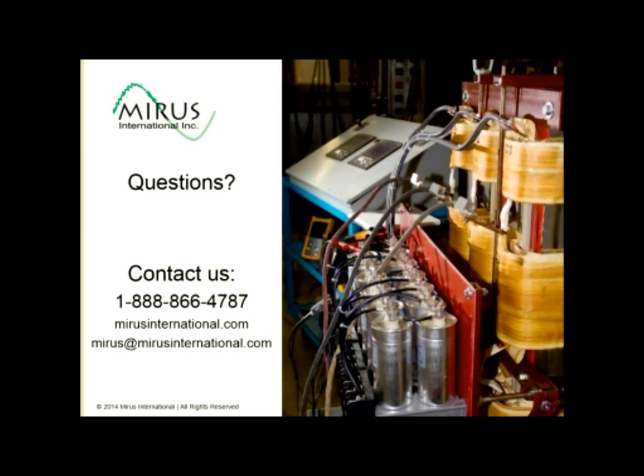There's a question: in a rural area where there are several installations of VFDs with filters and all the VFDs are off, would the capacitive reactance become an issue for the supply network? It's a good question. It really depends how many filters there are on the system, but typically the power system can handle some leading power factor, and if the power system is a quite stiff system, a fairly large system, or in rural areas sometimes they can be fairly weak systems, you'd need to look at the power system to determine whether that level of capacitive reactance is still suitable. But certainly as far as filters are concerned, the Lineator filter has the lowest capacitive reactance, so it is going to be the most suitable for that application.